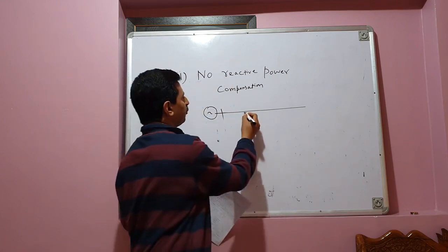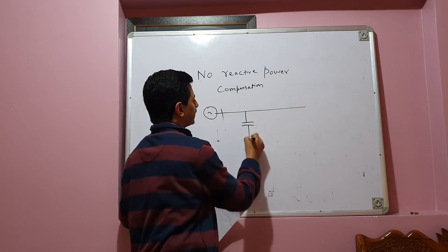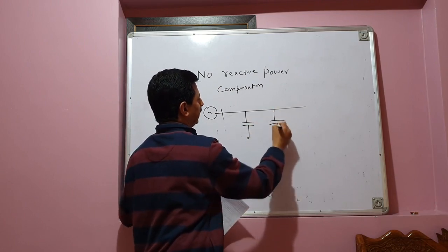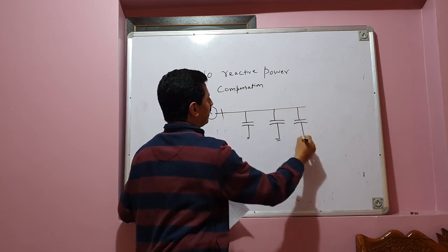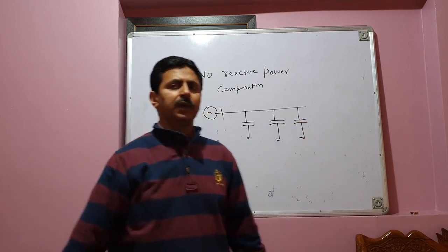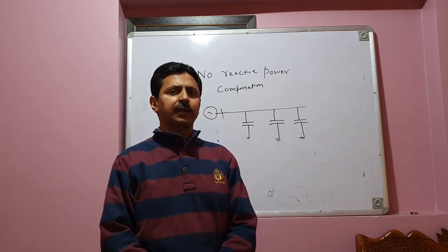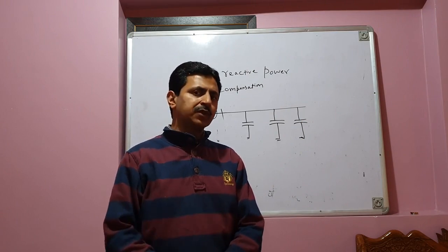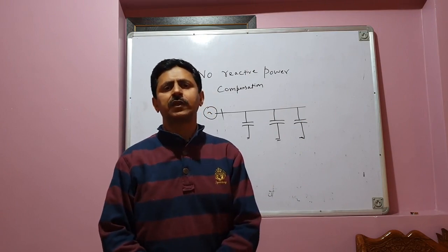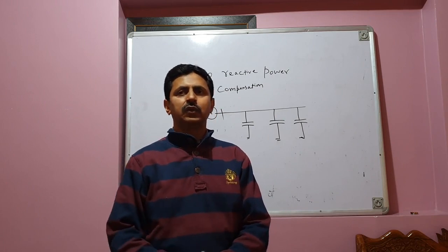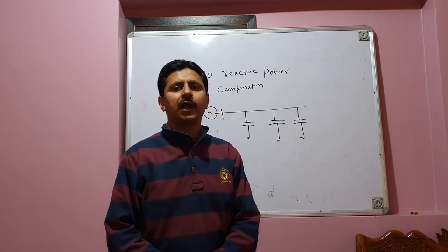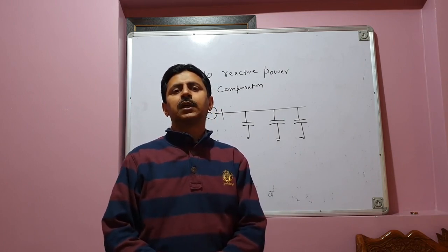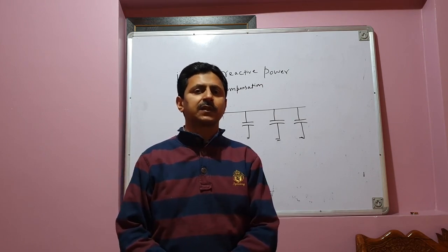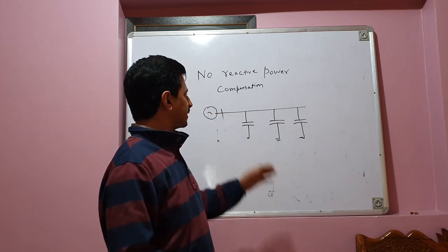So therefore, you need the reactive power compensators. The simple compensator is a bank of capacitors, shunt connected capacitors. And nowadays we don't use shunt connected capacitors. We use various FACTS devices, like SVC, static var compensator, or STATCOM, static synchronous compensator. What is the function of these shunt compensators?